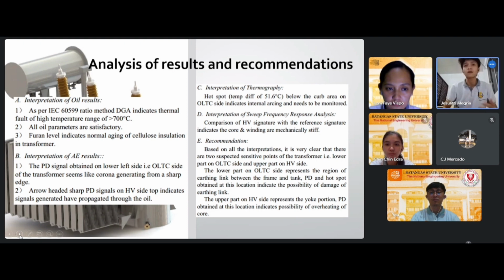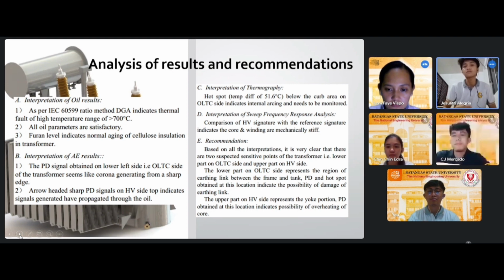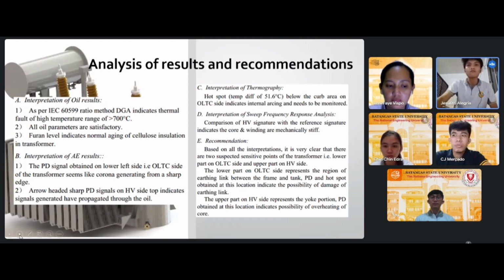The recommendations. Based on all the interpretations, it is very clear that there are two suspected sensitive points of the transformer: the lower part on the OLTC side and the upper part on the high voltage side. The lower part on the OLTC side represents the region of the earthing link between the frame and tank. The PD and hotspot obtained at this location indicate the possibility of damage to the earthing. That's why they must have preventive maintenance on the transformer. The upper part on the high voltage side represents the yoke portion. The PD obtained at this location indicates the possibility of overheating of the core.